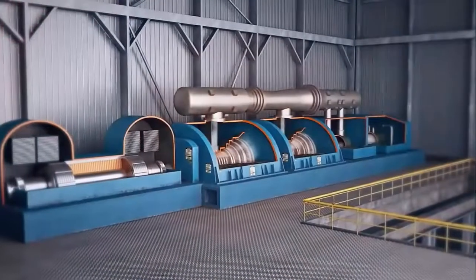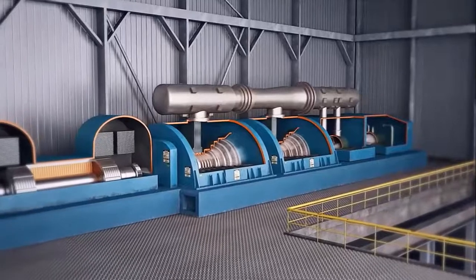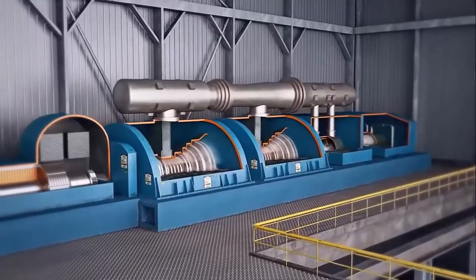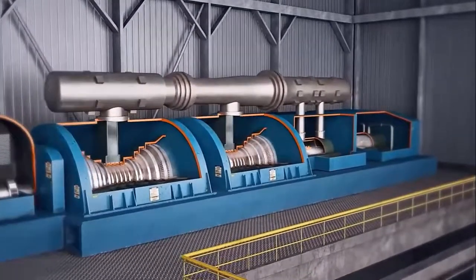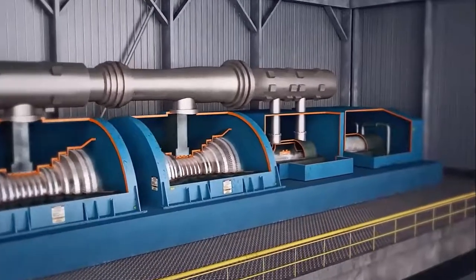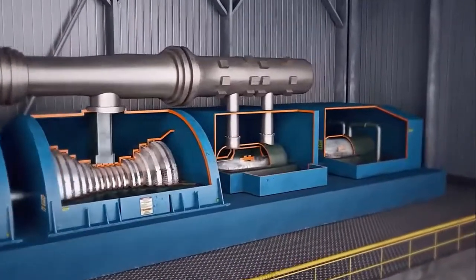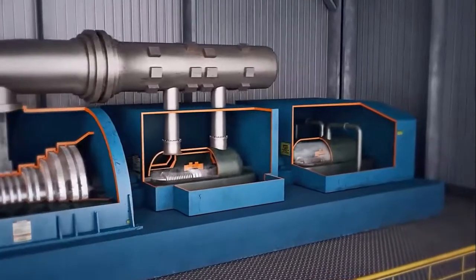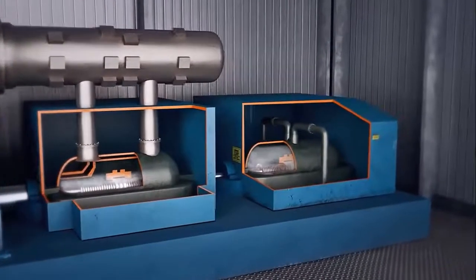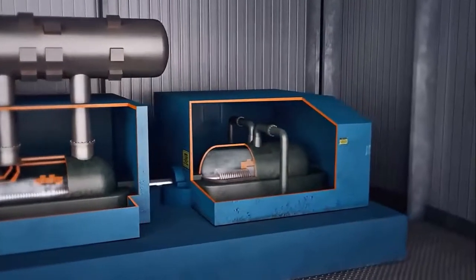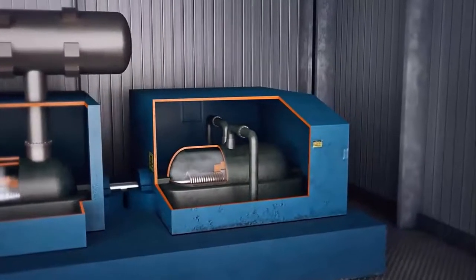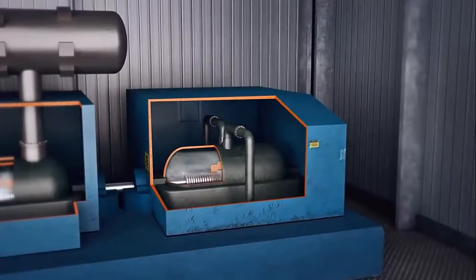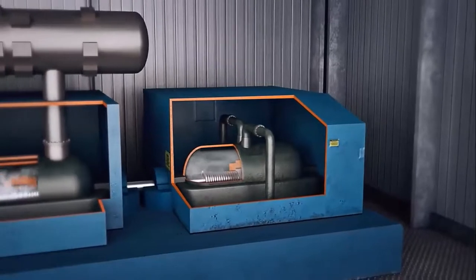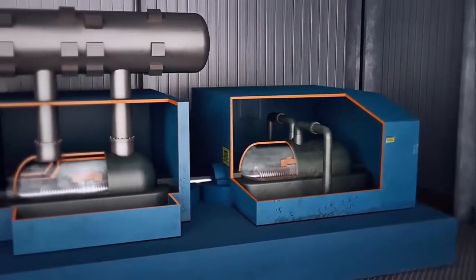Superheated steam from the boiler, which is approximately 2400 psi and 1000 degrees, travels to the high pressure section of the turbine, where it creates the force that turns the turbine shaft. This process causes the steam to lose temperature and pressure, so it must be sent back to the boiler to be reheated to 1000 degrees. After reheating, the steam returns to the intermediate turbine and continues through the crossover into the low pressure turbines.